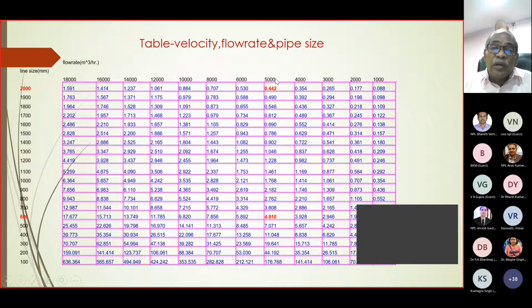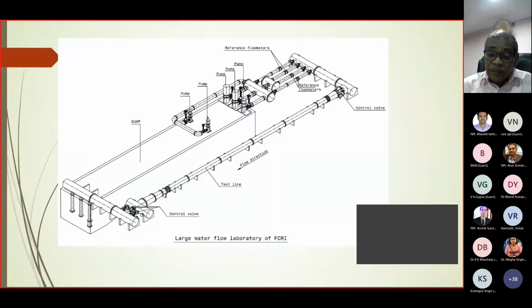For example, say your lab capacity is only 5000 cubic meters per hour. With a 600 mm pipeline, you will get 4.9 meters per second. But if you increase the line size for the same flow rate, what will happen? The velocity will come down. If you go for 1000, the velocity will be still less. If it is 2000, it is less than 1 meter per second. So you will have to compromise on velocity.